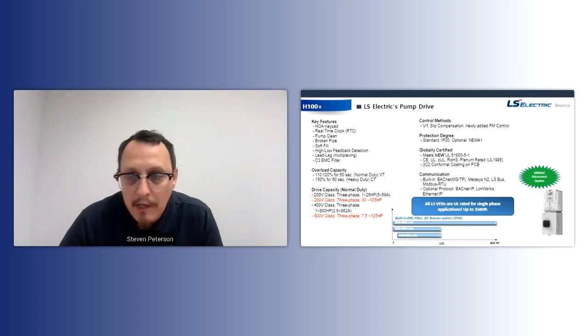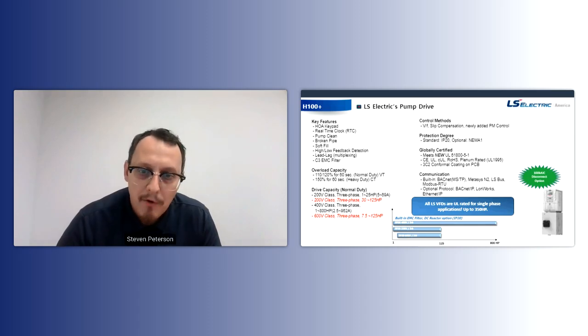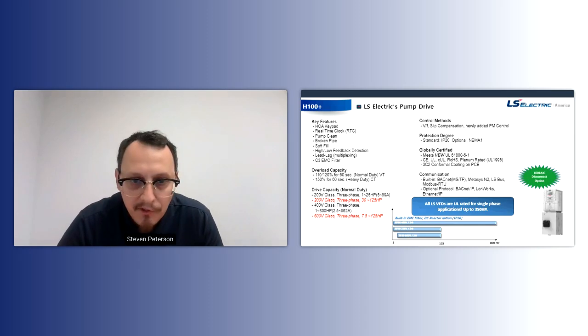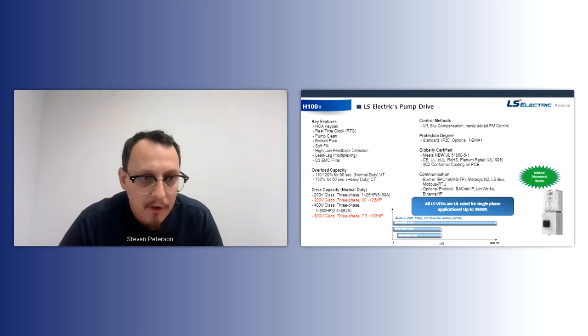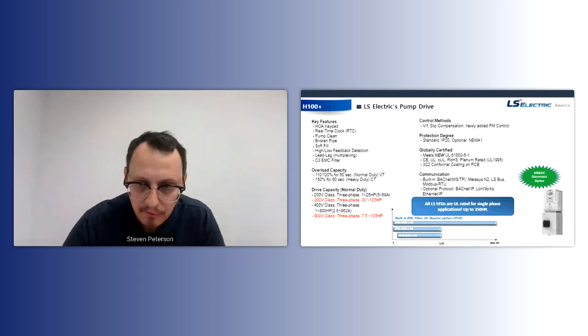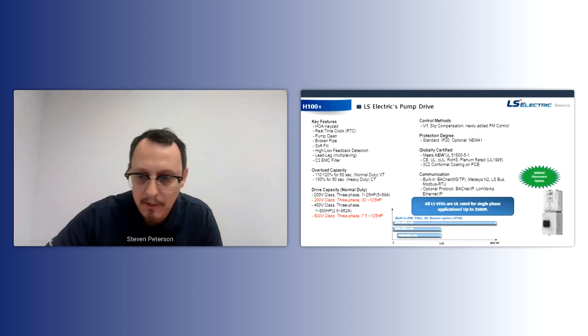So same thing for a 10 horsepower. If you applied single phase to it, it'd be a 5 horsepower drive because you're only running a single phase input. So we could do that on any of our drives. It's all been UL tested. We have sizing charts on our website, which we'll talk about a little bit later.